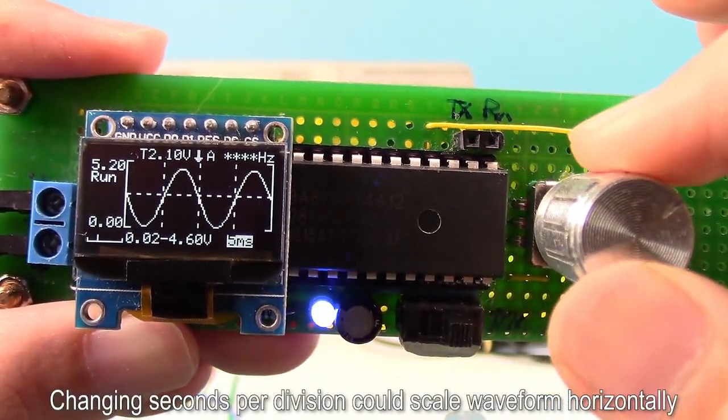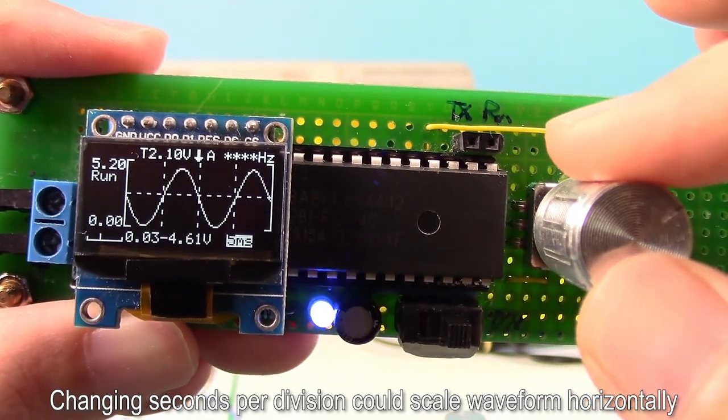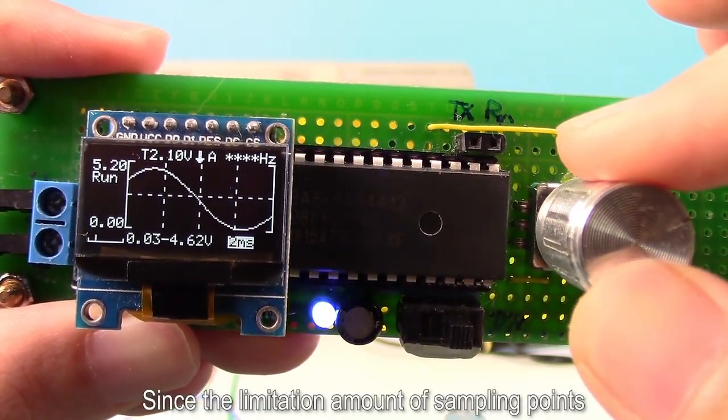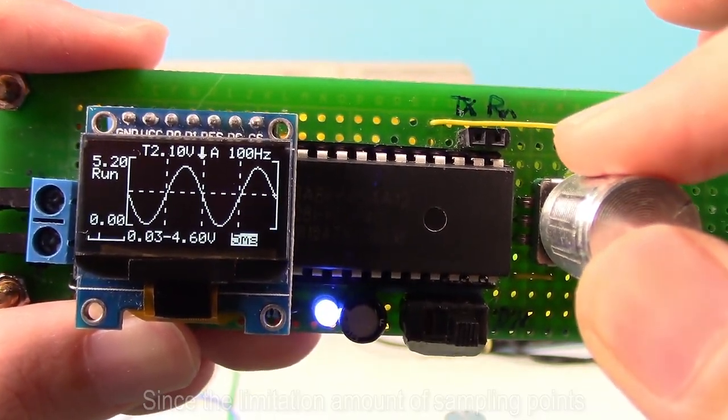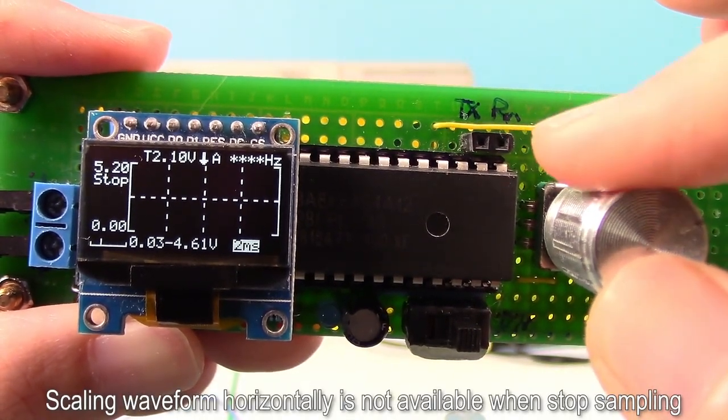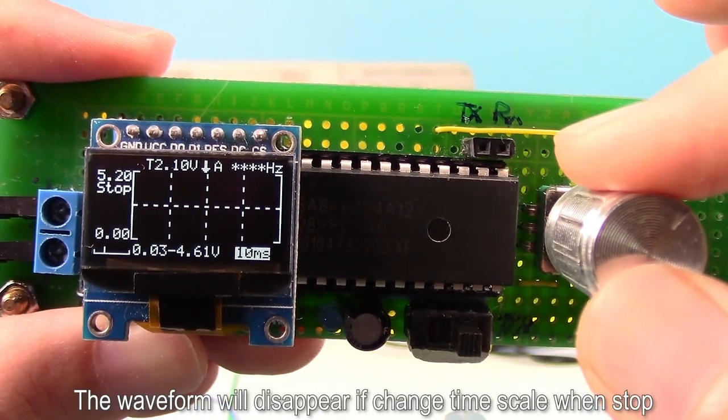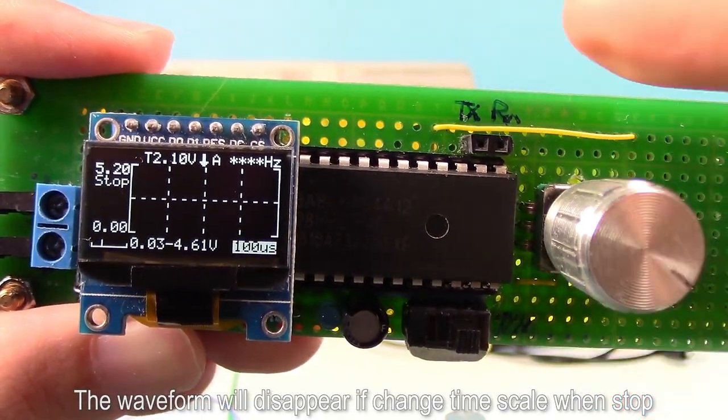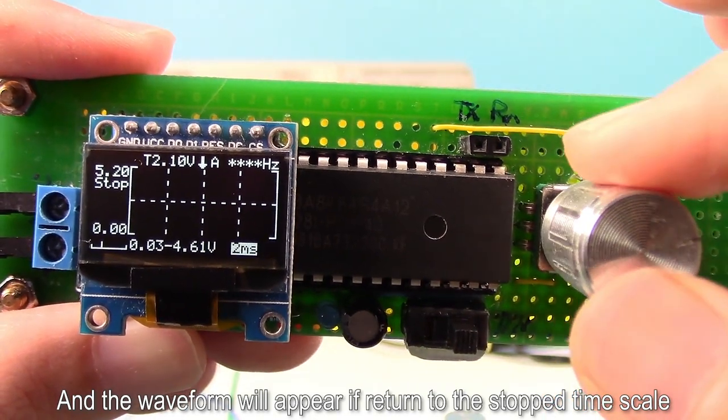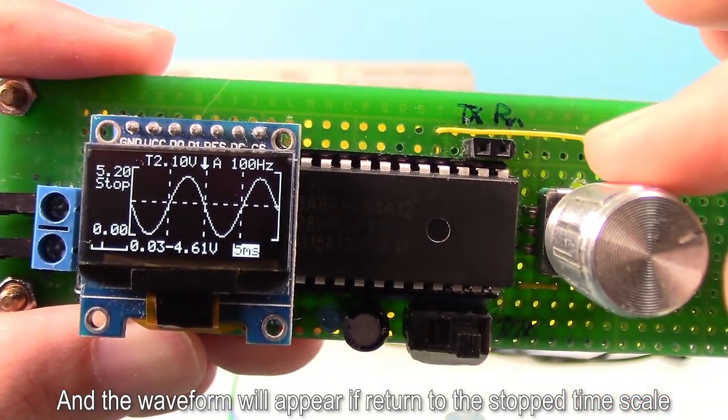Changing seconds per division could scale waveform horizontally. Since the limitation amount of sampling points, scaling waveform horizontally is not available when stop sampling. The waveform will disappear if change timescale when stop, and waveform will appear if return to the stopped timescale.